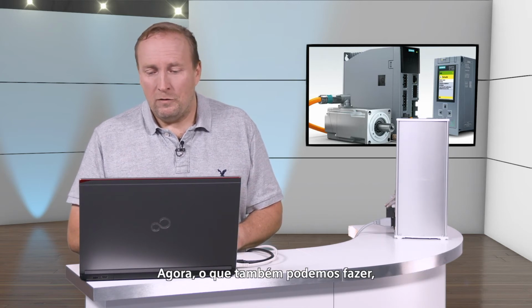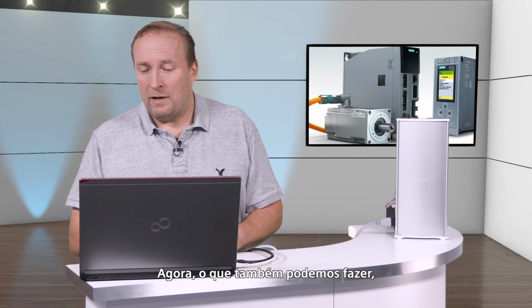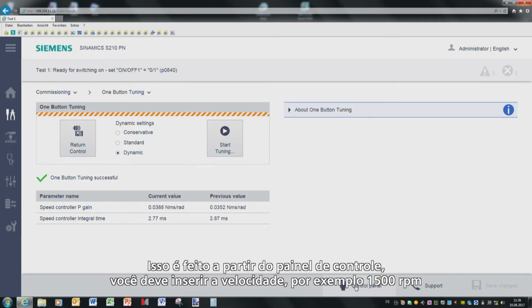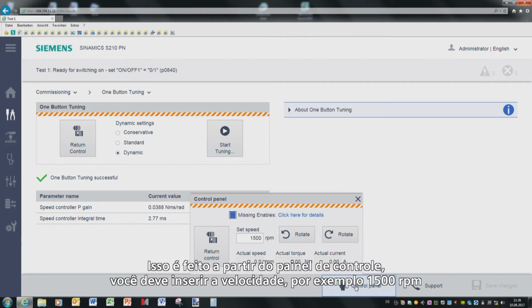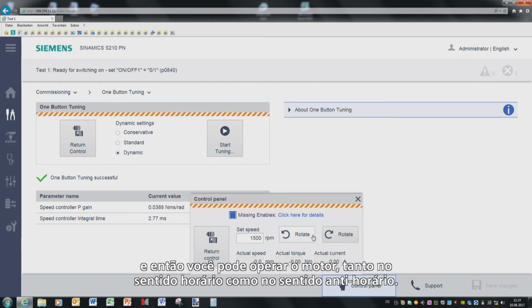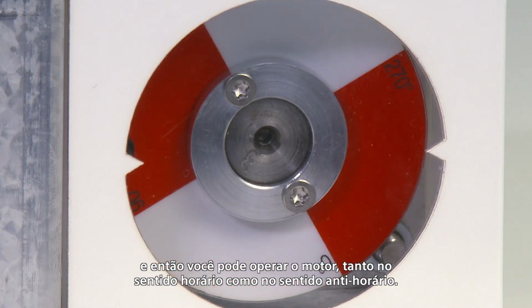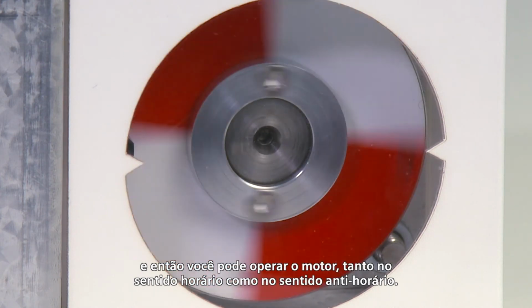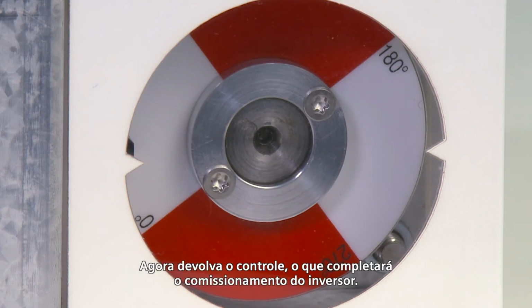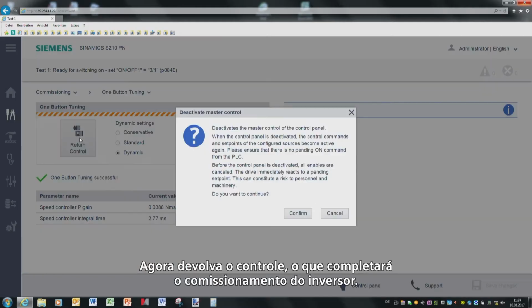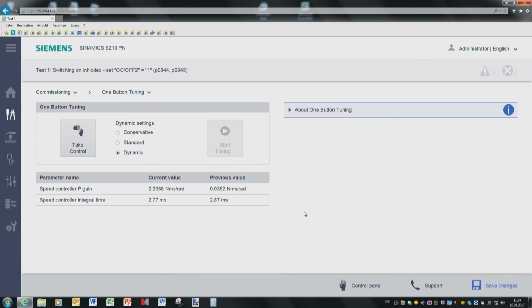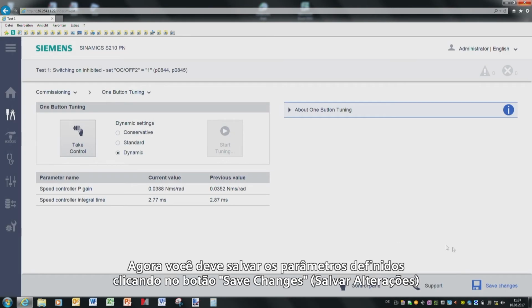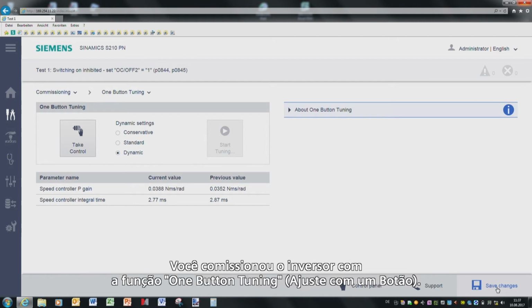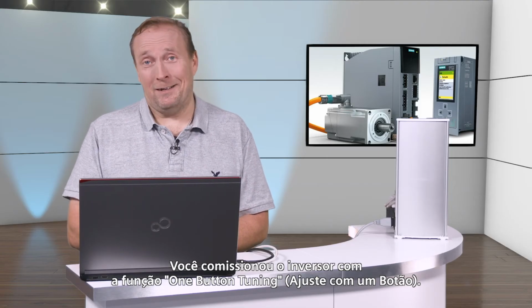Now what you can also do is operate the device manually. This is done from the control panel. You must enter a speed, for example, 1500 revolutions per minute, and then you can operate the motor, either clockwise or counterclockwise. Now, return the control, which completes commissioning the drive. You must now save the parameters that you have set by pressing the Save button. You have now commissioned the drive with one-button tuning.